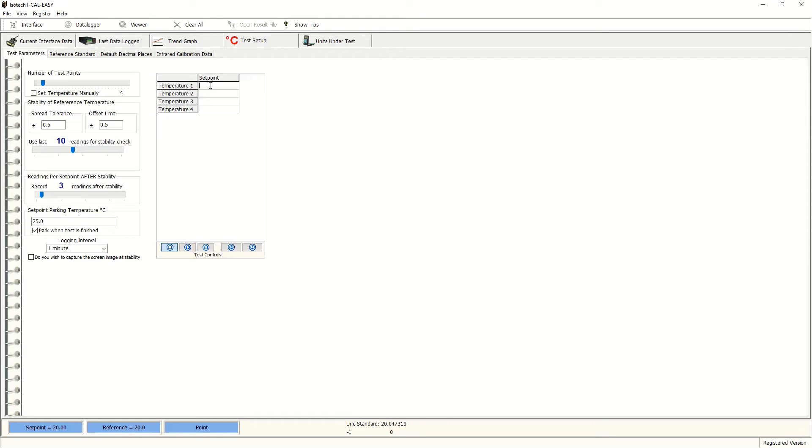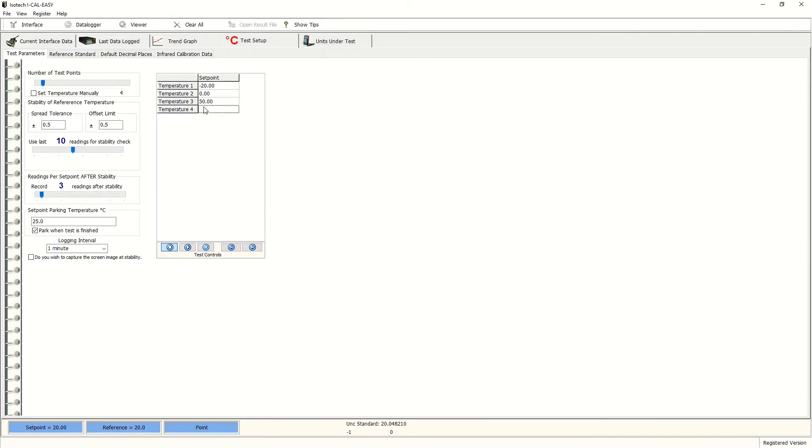Our dry block can do negative temperatures. So we'll start at minus 20 degrees C, up to zero degrees C, 50 degrees C and 140 degrees C. We will have to remember when this has been reached and finished to park the dry block at a safe temperature.